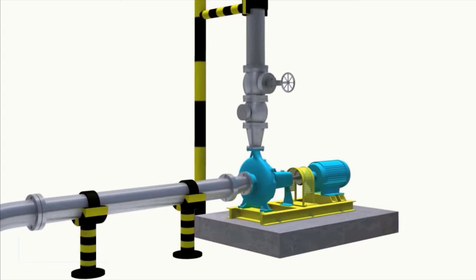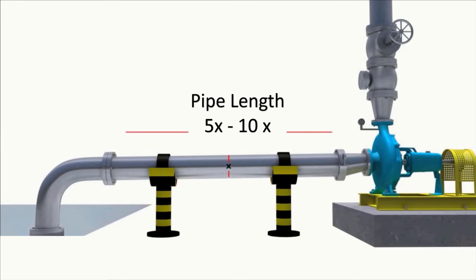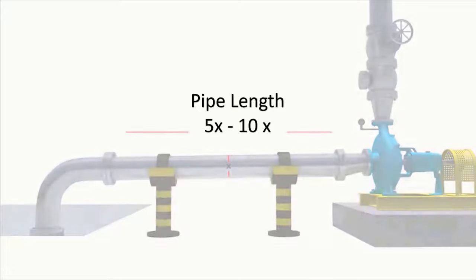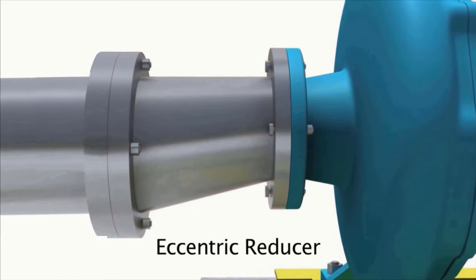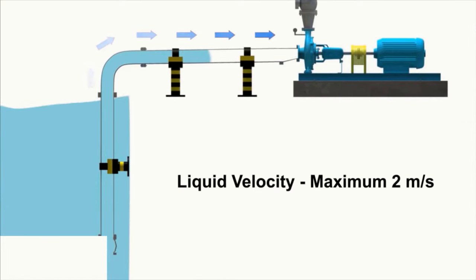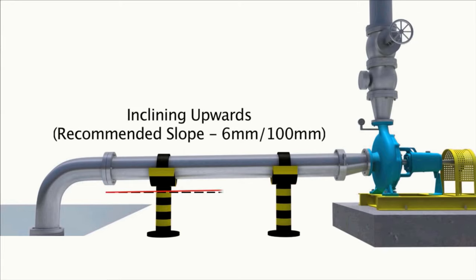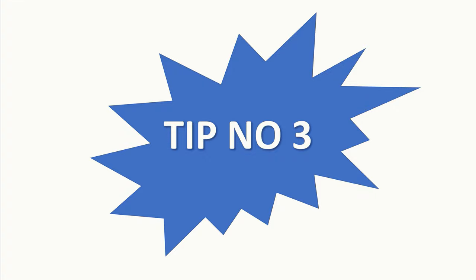Tip number two: follow good engineering practices for piping design. One recommendation is a minimum suction straight length of 10 times the suction flange diameter — but at least keep a straight length of five times the diameter to minimize recirculation. Have smoother transitions when you have reducers or elbows along the way. The rougher the path for the liquid, the higher the friction losses and turbulence, and the greater the chances for damaging cavitation.